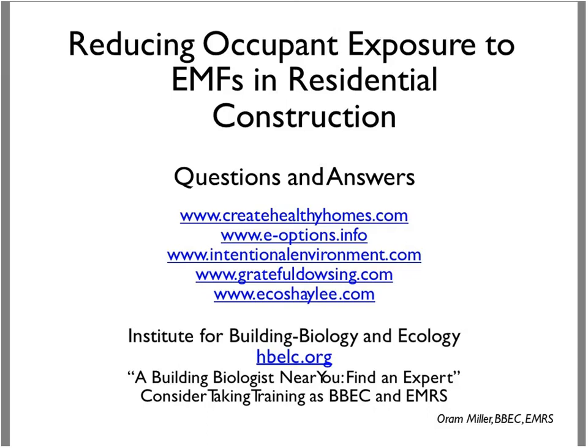But something else I want to point out: there are three manufacturers I know of for in-floor radiant electric heat, SunTouch, Innotherm, and Danfoss. What they have is dual conductor technology. Instead of running the hot wire out, zigzagging back and forth, and then running the neutral or return wire back along one side, which gives zero cancellation and a high magnetic field, they run the hot wire out all the way to the end and circle it back so the return wire is right alongside the outgoing wire at all points. As you've learned earlier today, the magnetic fields then cancel each other.